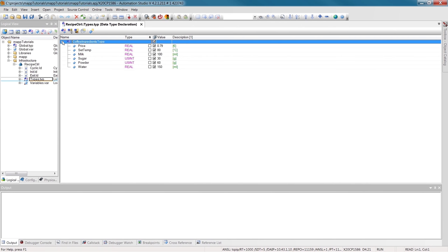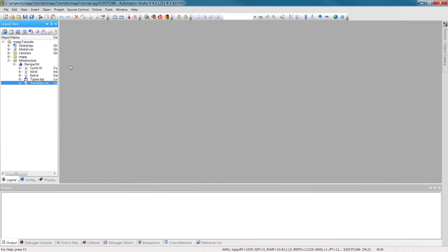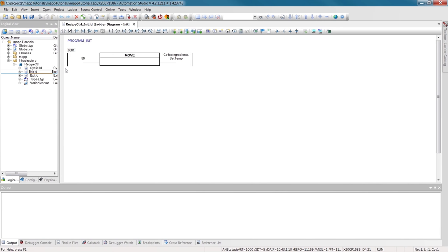I've already created the structure CoffeeIngredientsType, which contains the parameters that you see here. CoffeeIngredients is our process variable. What we want to do is save the variable, with the values we've just seen, as a recipe. The process variable needs to be used in the software so that memory is allocated for it, so I'll call it in the initialization subroutine.